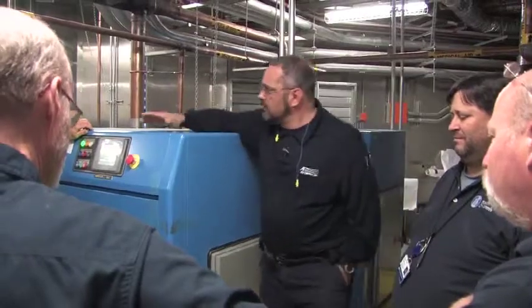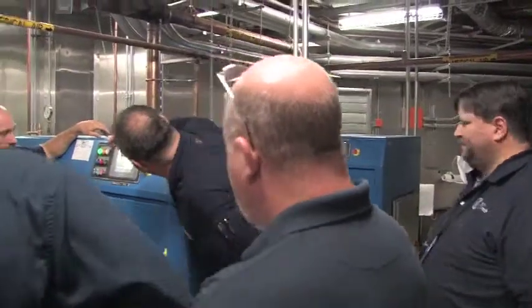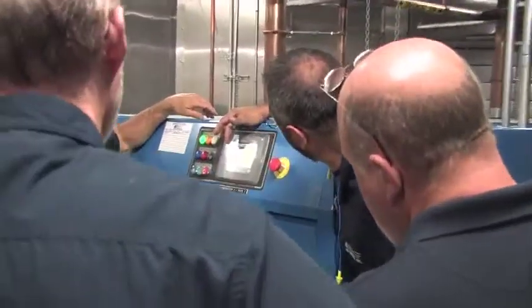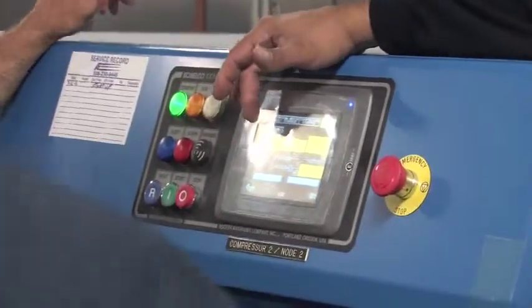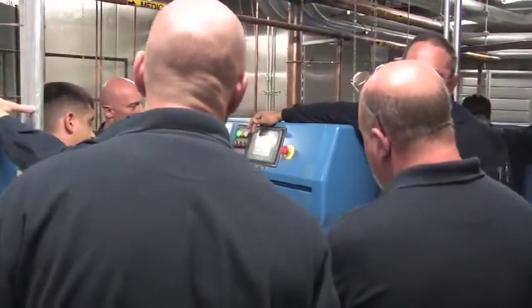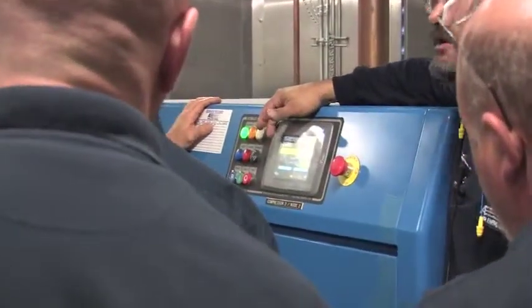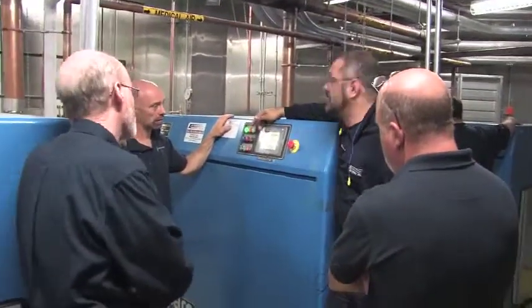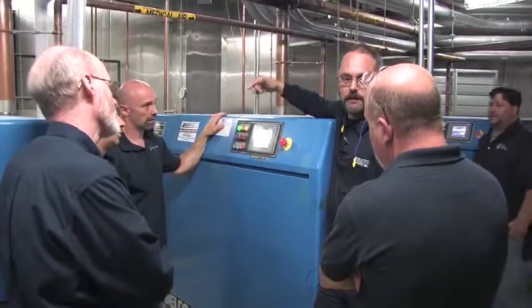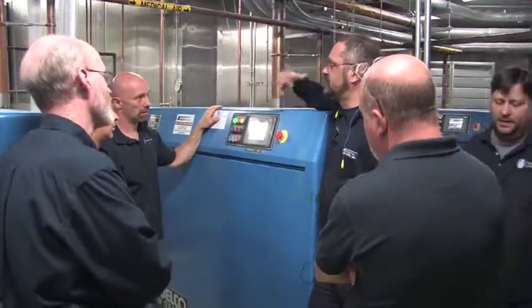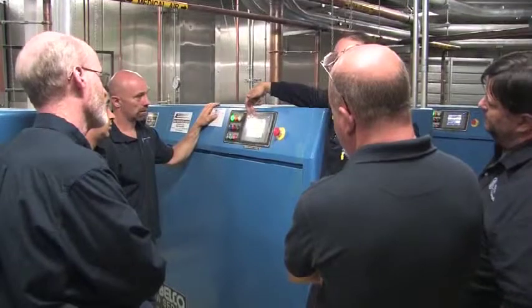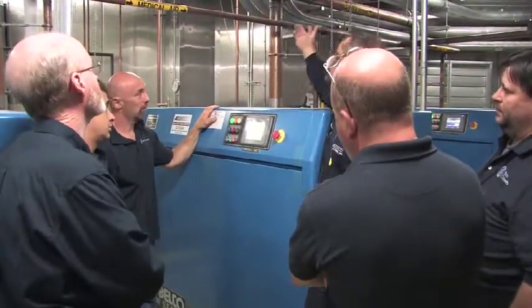So most important thing, when you're looking at the screens, like all the newer ones, you've got the main screen here that gives you inlet pressure. This is new. Your older ones don't have this. No, we just got the interstage and the outlet. They now have an inlet pressure gauge, so you can tell what the restriction is at the throat of the pump. Now the interesting thing about that is if your inlet filter is brand new, that's also telling you what your delta is on your intake pipe. So for example, if all three of these try to run and load, that's going to go a lot lower because they're all trying to pull enough air to compress down that one intake pipe.